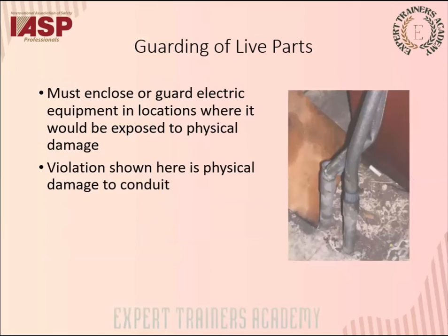Guarding of live parts. Electrical equipment must be fully enclosed or guarded in locations where it could be exposed to physical damage. See, in this picture, there's a violation here, which is physical damage to the conduit. Which must not be. That might lead to an electrical risk.